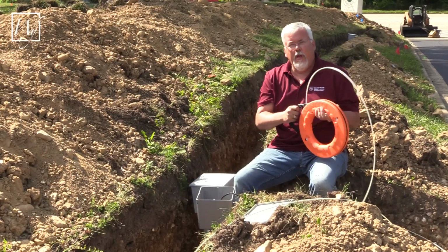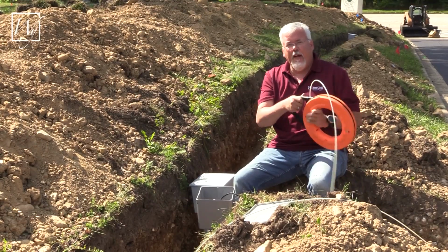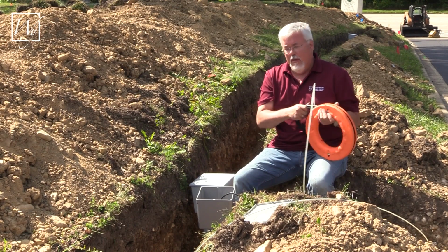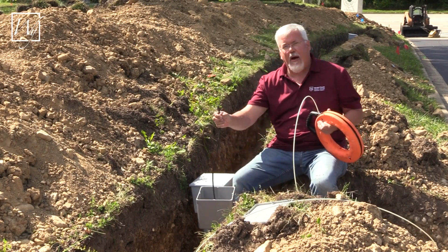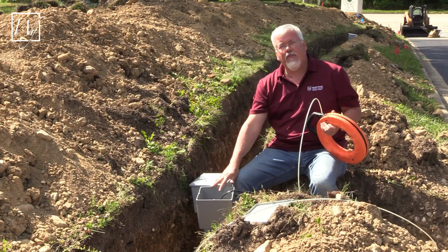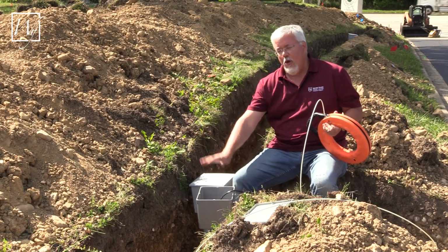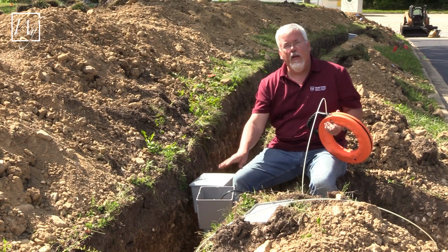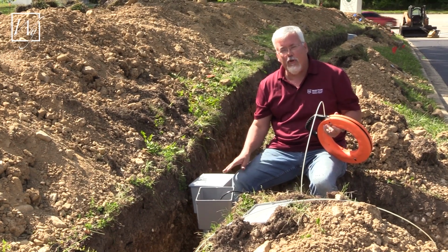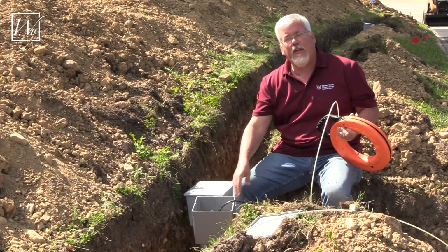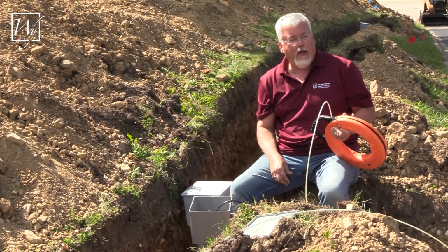We've used our fish tape and gotten our cable out of the junction box. Notice there are two junction boxes here, one for high voltage, one for low voltage — you never run low voltage in the same box as high voltage. So we're going to continue pulling the cable out until we get the sensor ready to set.